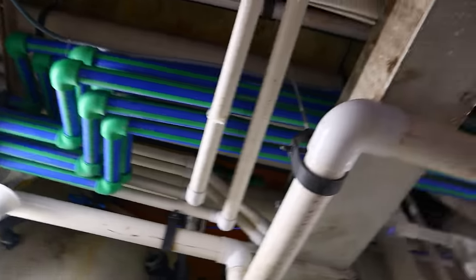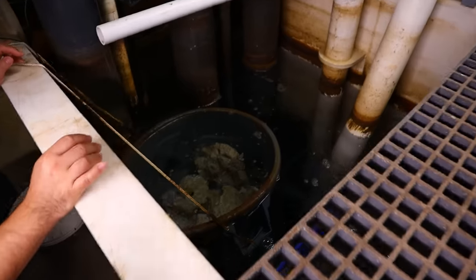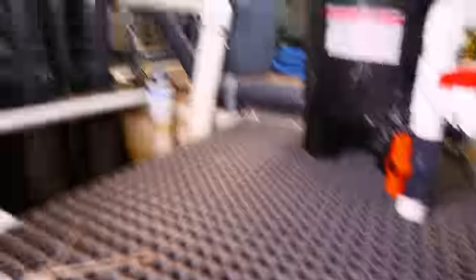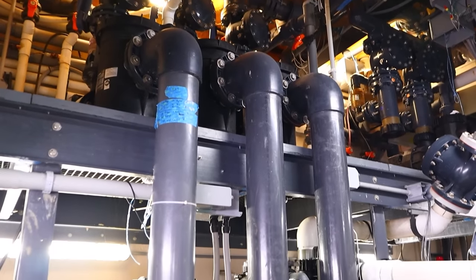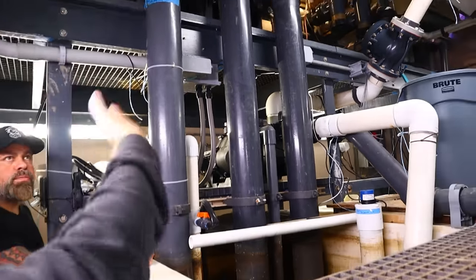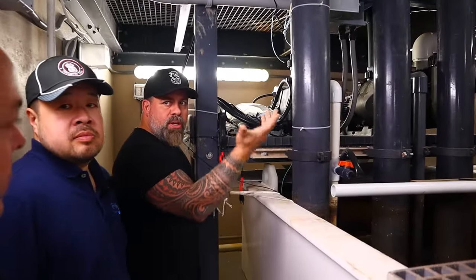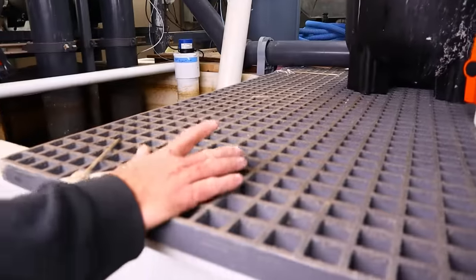We have dehumidification just for down here. The sump for the 17,000-gallon tank is 12 feet long, 4 feet wide, and 8 feet deep total — actually buried in the ground. It has three 10-horsepower pumps supplying water to the tank: two running, one spare, cycling every 24 hours. If there's an emergency, it picks whichever pump is capable and ramps to full capacity. Everything is made of fiberglass and 316 stainless steel.